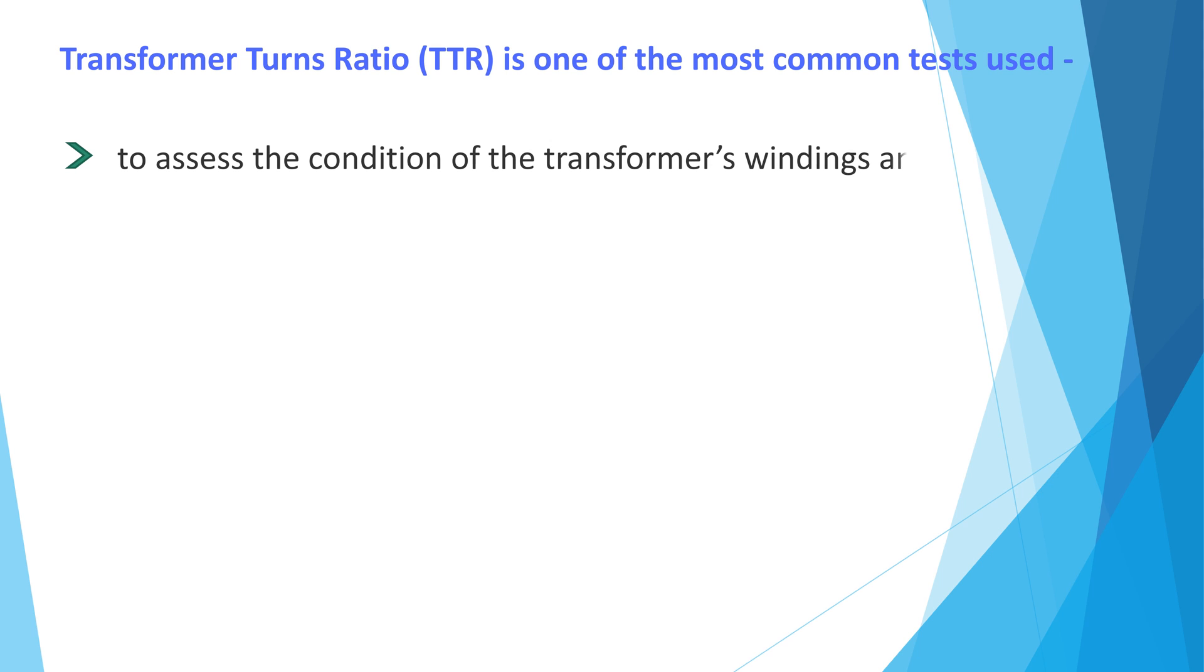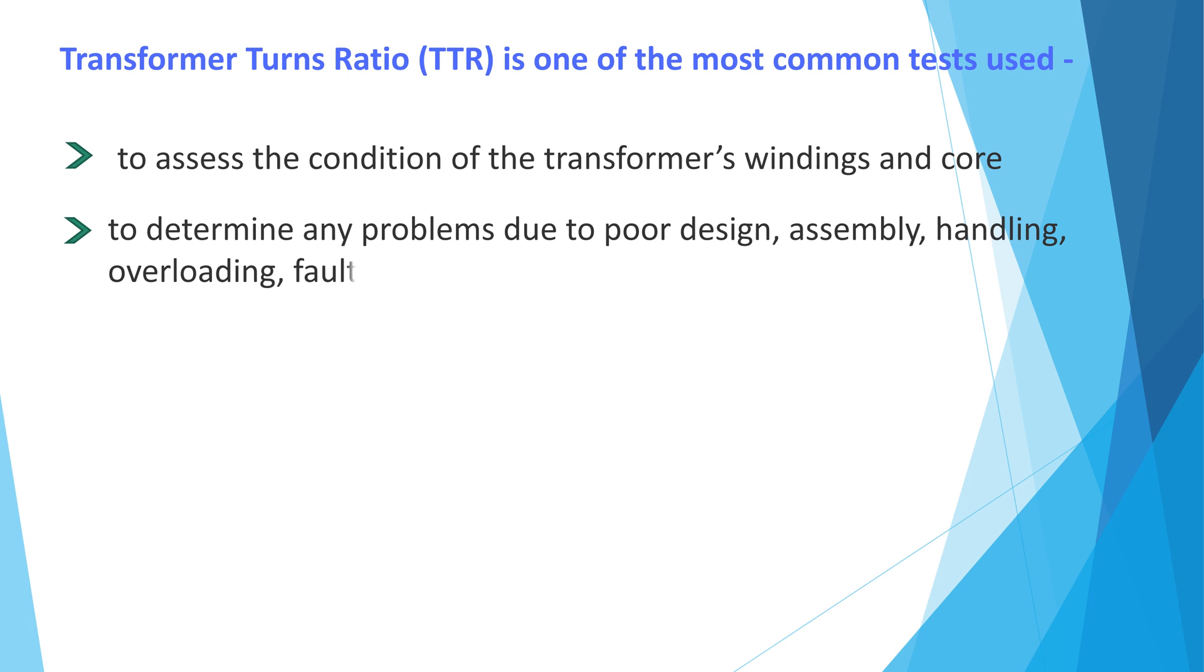Transformer turns ratio TTR is one of the most common tests used to assess the condition of transformer's winding and core, to determine any problem due to poor design, assembly, handling, overloading, fault conditions, and poor maintenance.